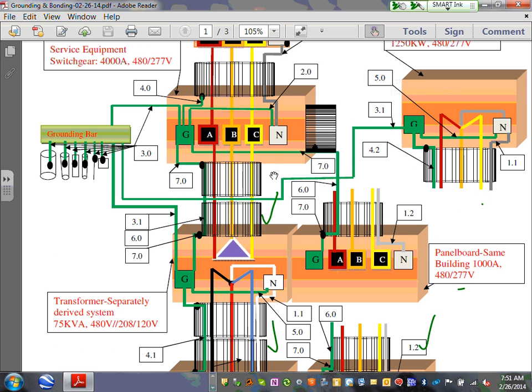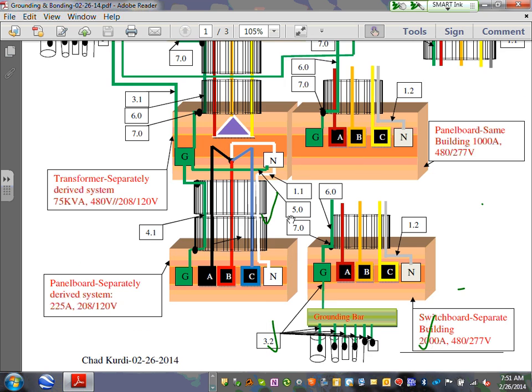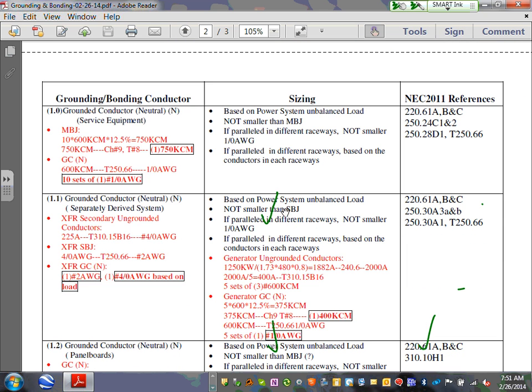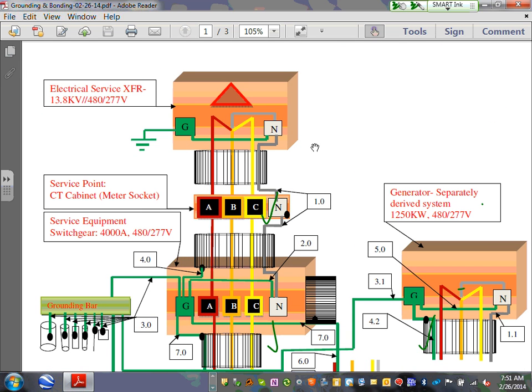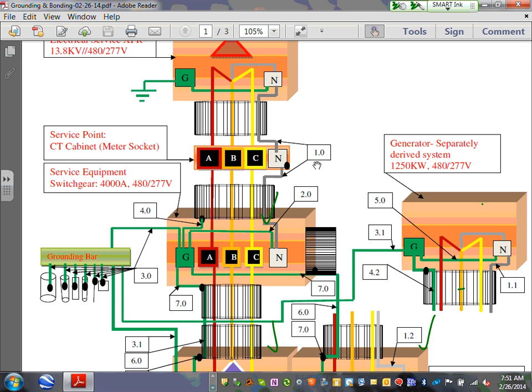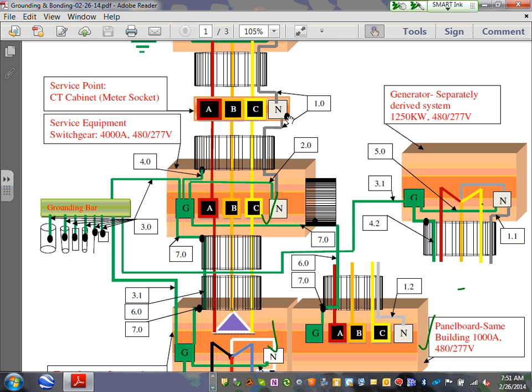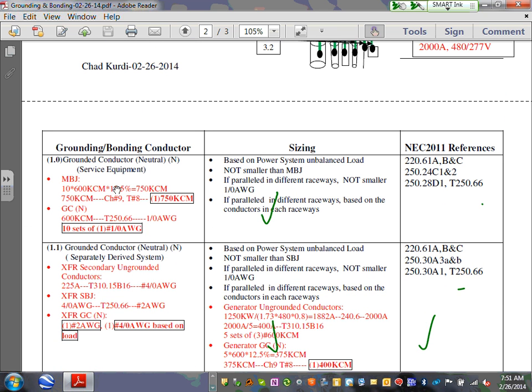So for each one of these, the green is my focus. The focus right now is to do grounding and bonding at the green. So I want to bring to your attention, Adam, if you see 1.0 right here. So 1.0, can you guys see that right here? 1.0, it's called the grounded conductor. Everybody can see the grounded conductor. And right here, let's say what the grounded conductor is. The grounded conductor is at the service equipment. How do you size it?